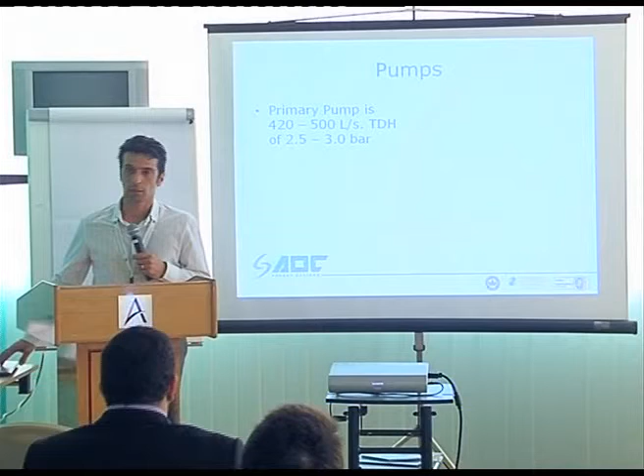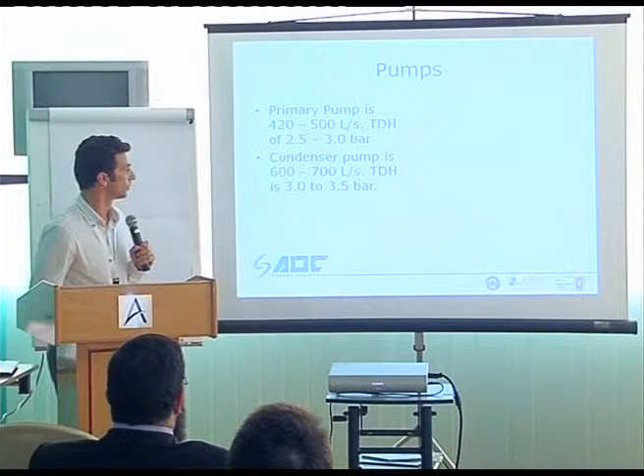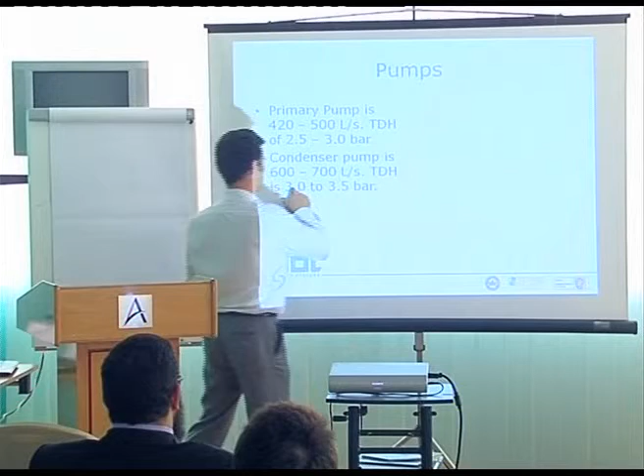Pumps, from primary pumps, which if you do your calculations, and I'm sure you will go back today to the hotel to do your calculations on the district cooling plant, you will find it's around 420 to 500 liters per second. To be exact, on a 16-degree Fahrenheit chilled water plant, it will be around 473 liters per second. The pumps in a primary-secondary system is around 2.5 to 3 bar. A condenser pump has a higher range because it has to take the heat of the compressor as well up to the cooling towers. A total developed head of 3 to 3.5 bar.